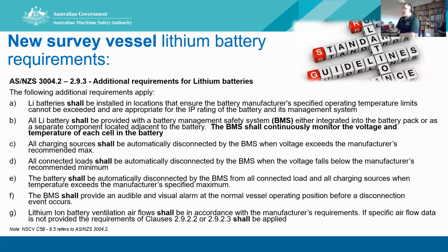All charging sources shall be automatically disconnected by the BMS when the voltage exceeds the manufacturer's recommended maximum. All connected loads shall be automatically disconnected. I'm stressing shall again. When the voltage falls below the manufacturer's minimum, the battery shall be automatically disconnected by the BMS from all connected loads and all charging sources when temperature exceeds the manufacturer's specs. The BMS shall provide an audible and visual alarm at the normal vessel operating position before a disconnection event occurs. So that's to give the operator a chance to throttle back so they're not putting as much load on the battery and possibly reducing the temperature so they can continue operation.